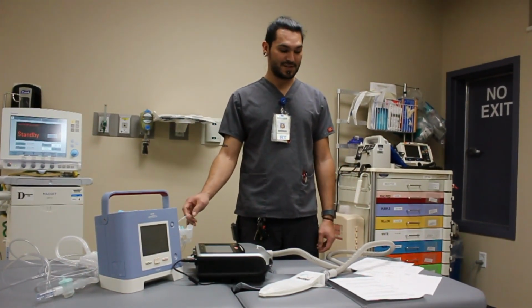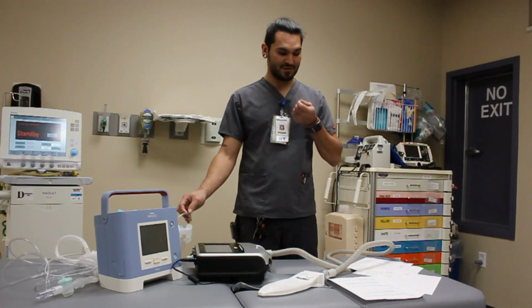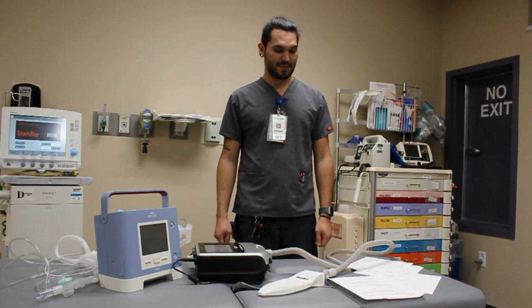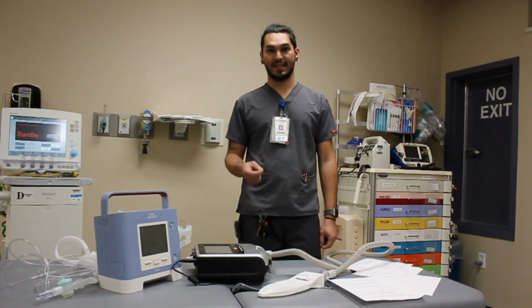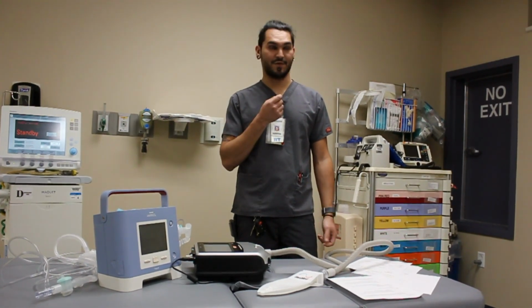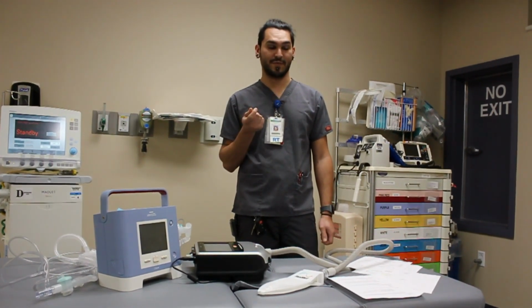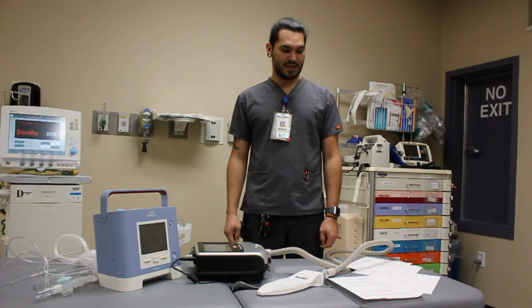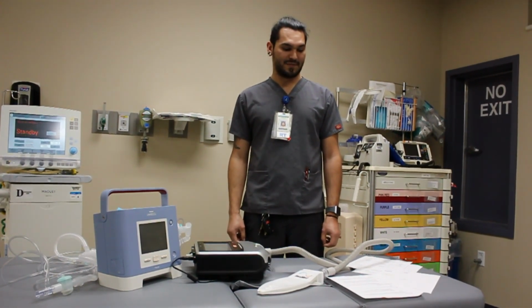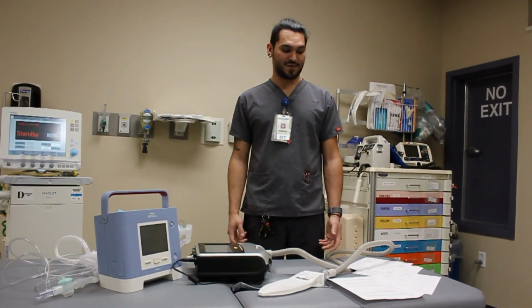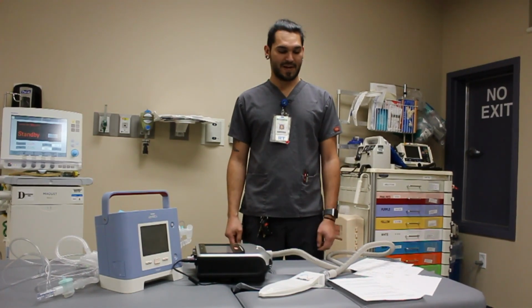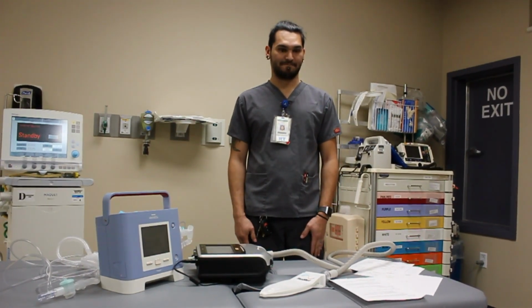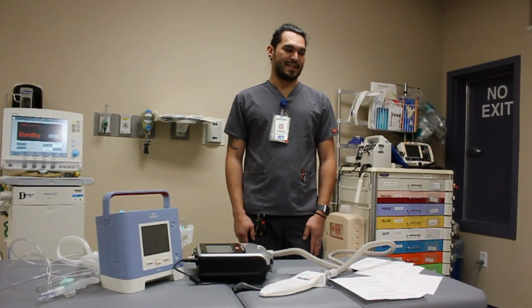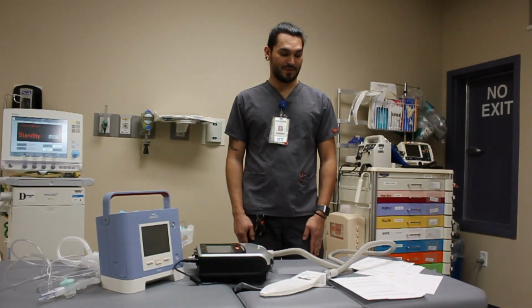We would look at the patient. We would suction, try to clear secretions. For trach patients, if we can't pass the suction catheter, your first thing would be to go ahead and remove the trach and replace it. If there's not a trach in place and there's not an obvious obstruction, there's always bagging the patient and calling RT. The next alarm, we're going to go over our low pressure alarms.